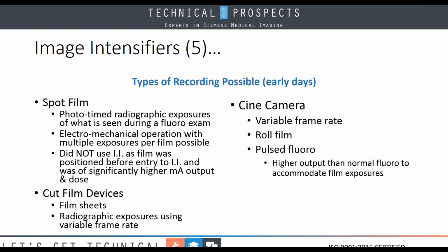An early example of another camera that was used in the day was something called a cine camera. Here we used roll film that would be sitting and mounted on a camera, and we had a variable frame rate anywhere from 15 to 120 frames per second, where we would be flipping through and making x-rays and pulse the fluoro exam or pulse the fluoro beam at a higher MA in order to expose this film, and we would create a motion picture. Of course, the hard part was developing that roll of film and then hoping that we got everything good.